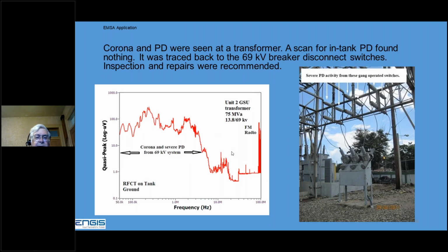This particular one is down in the Dominican Republic. We tested this transformer: broadband corona, severe partial discharge activity, very strong FM radio station. No AM radio could be seen. It's covered up by this noise. We used the sniffer and we scanned the tank and found no partial discharge activity at the transformer.